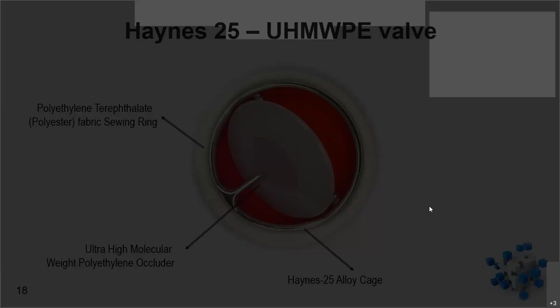Now, these are the fabrication strategies for the valve. We have the Haynes 25 cage, which was CNC machined from a solid metallic block and polished to prosthetic quality. Then this ultra-high molecular weight polyethylene was not a material which can be easily processed. The conventional injection molding and compression molding techniques were not suitable for this. So we needed to develop two specific processing strategies, which we call the solid state compaction technique along with the cryo machining technique, in which the component is cooled to sub-zero temperatures during the machining process, and the solid state compaction is used for imparting the surface finish of the disc. Then the polyester suturing is normally stitched using polyester sewing fabrics.